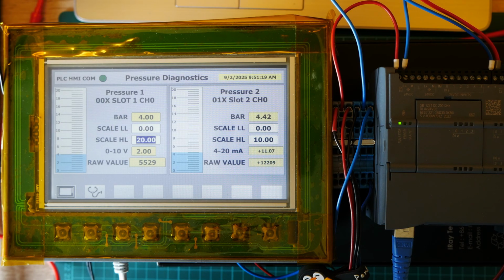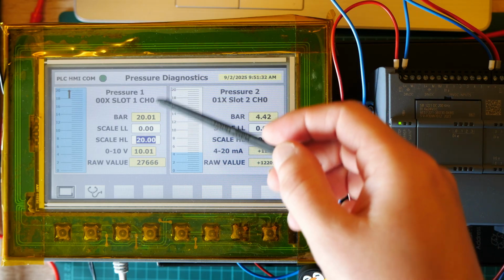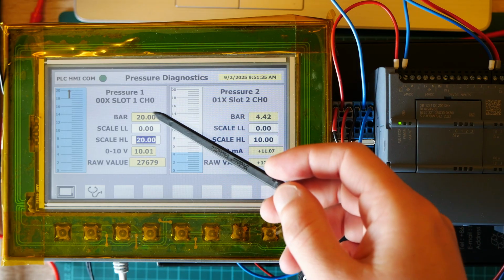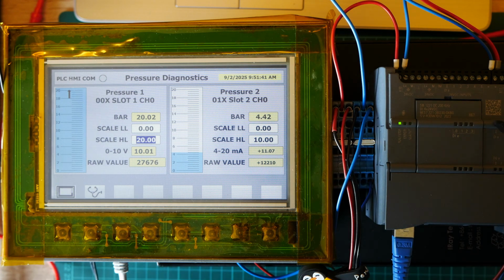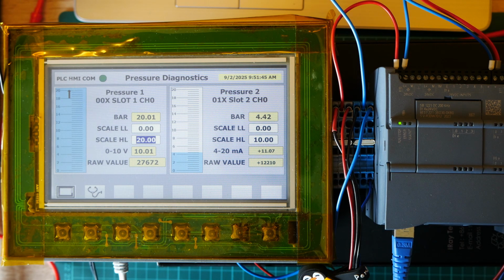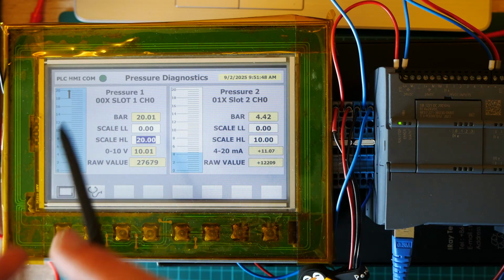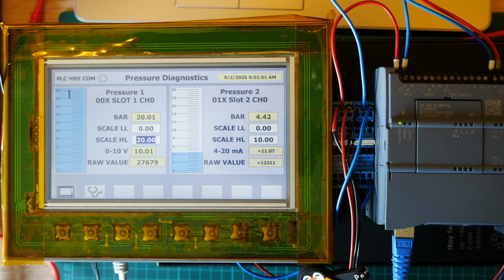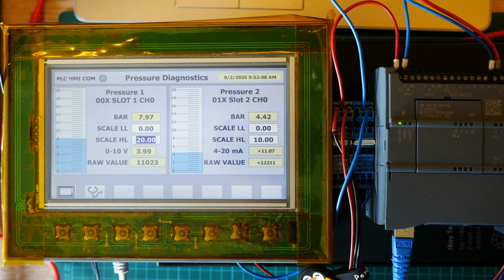So I will sweep the range. Okay, 4, 5, 6, 8, 9, 10. So if I sweep the range and these values correspond to what it should show, that means that the PLC program and analog input module are healthy. It definitely means that if you have some sort of problem, the problem is either in the wires or in the sensor itself. So at least you know where to look. Change wires. If that doesn't help, change the sensor.